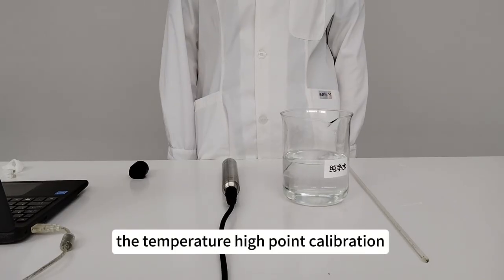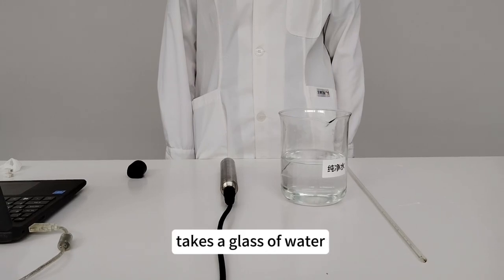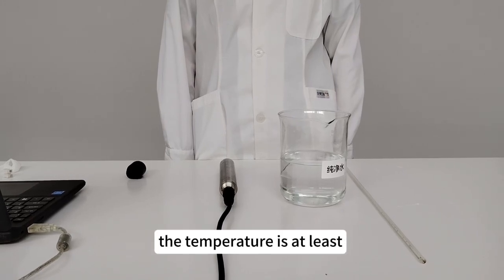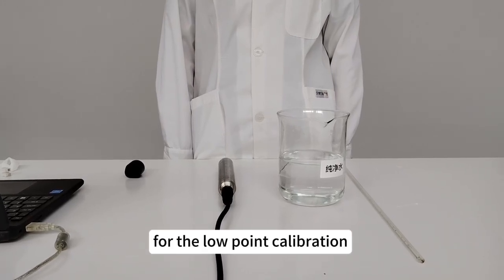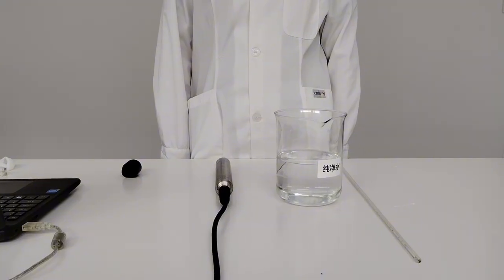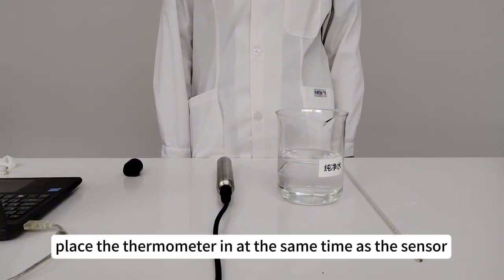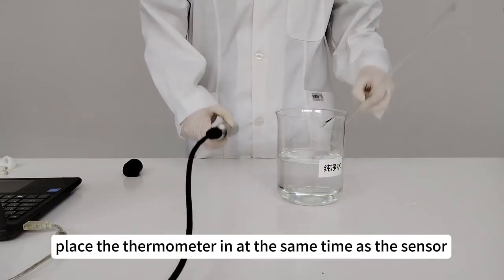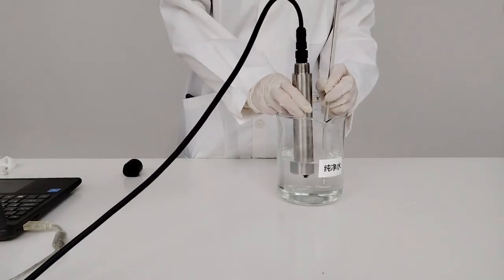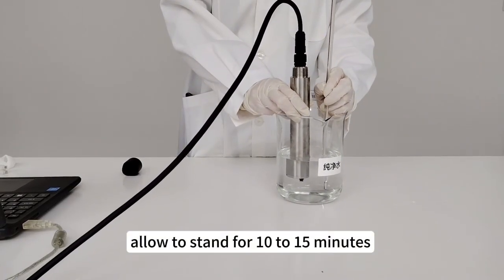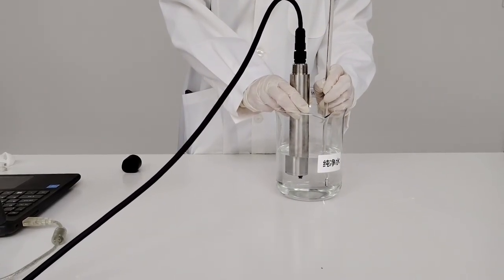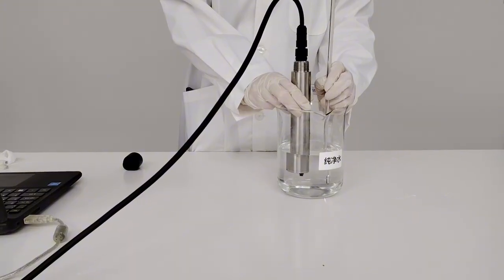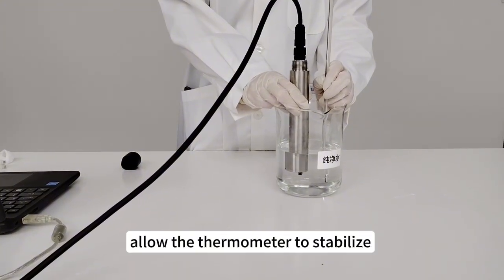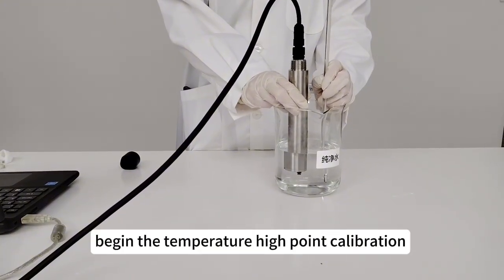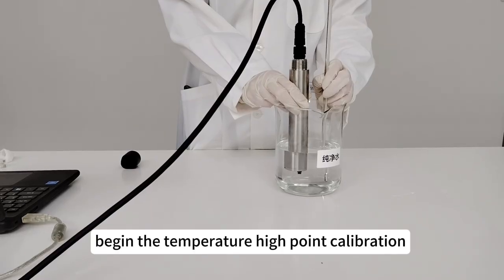The temperature high point calibration takes a glass of water. The temperature is at least 5 degrees warmer than the water for the low point calibration. Place the thermometer in at the same time as the sensor. Allow to stand for 10 to 15 minutes. Allow the thermometer to stabilize. Begin the temperature high point calibration.